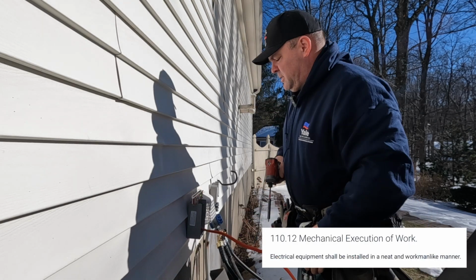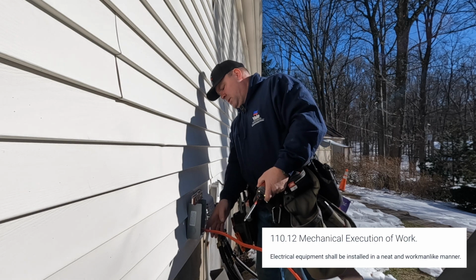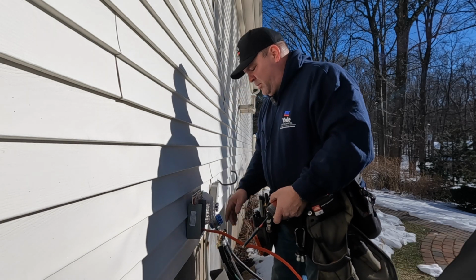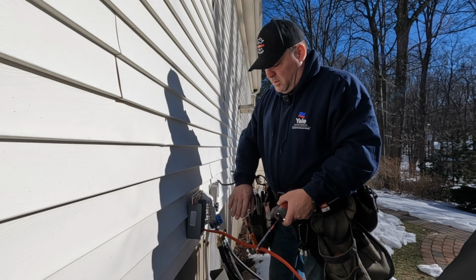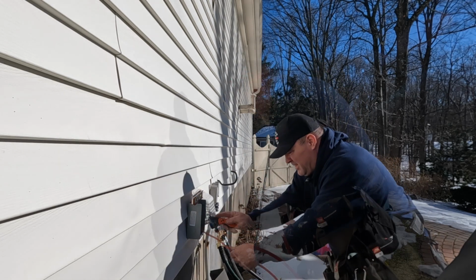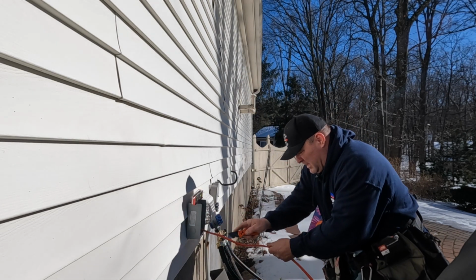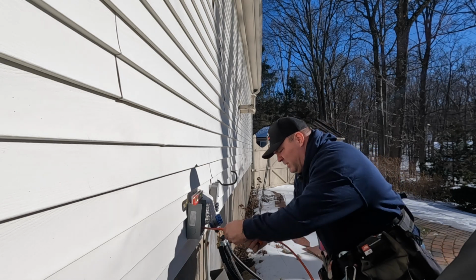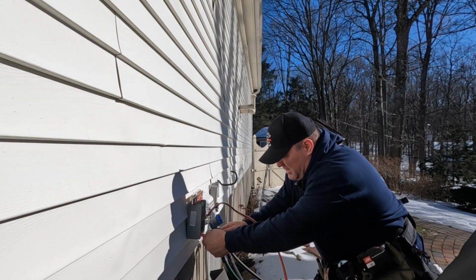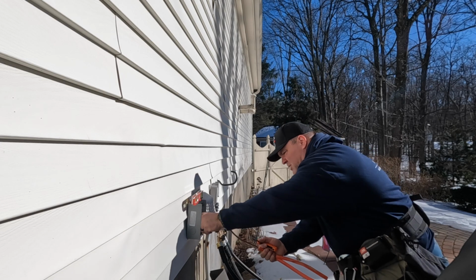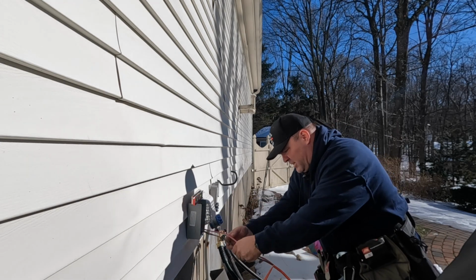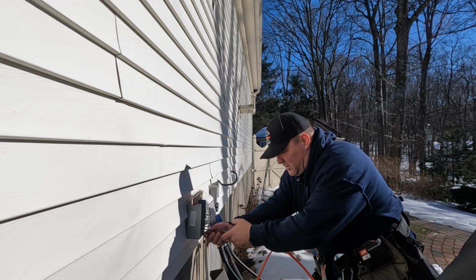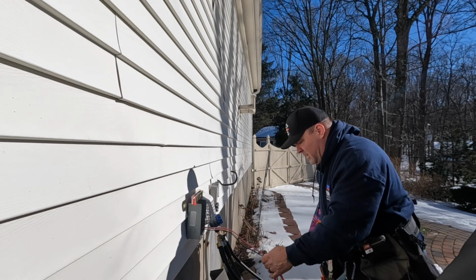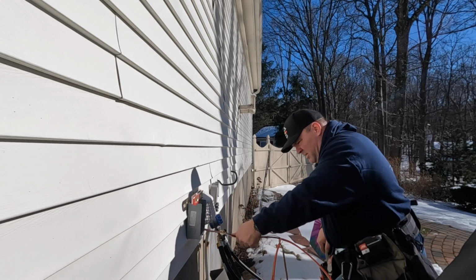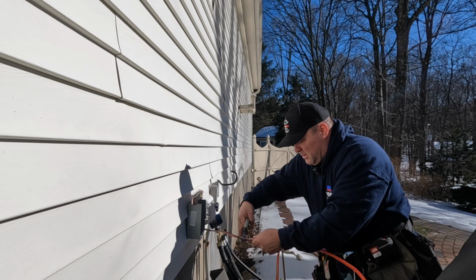Now, I do like to get this enclosure a little bit lower, a little bit close to the house on the top, so when the water collects on it, it'll roll off and not behind it. And so now I'm ready to peel back the sheathing here. Just going right down the middle of the sheathing and cutting back the edge like that. Now I know the circuit breaker's not on because I just put the interlock on, right? And with the interlock there, it's impossible for this circuit to be on unless the main breaker's off.